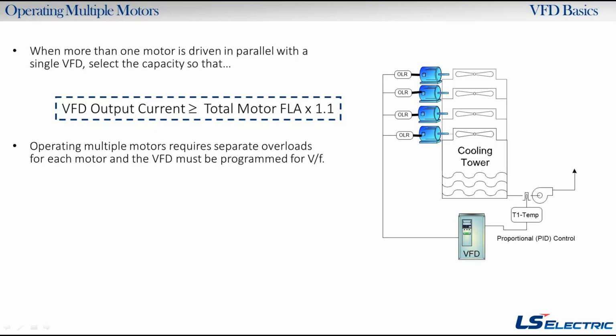The drive's just going to see the sum of all the currents, and it's not going to trip out when it should, so you could damage your motor, and then you can't complain to us because we said, oh, we told you to run separate overloads. So you always want to run separate overloads. So if that motor gets too hot, or it's overloading, then it cuts off the drive, for example. We'd recommend running that back to an external trip.